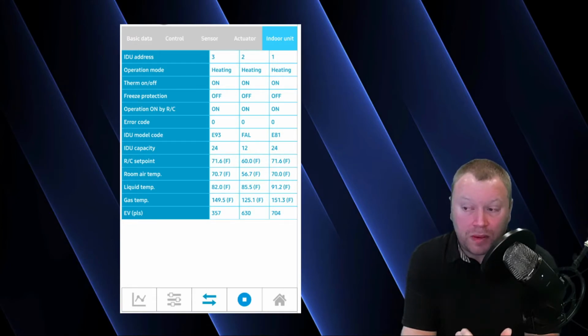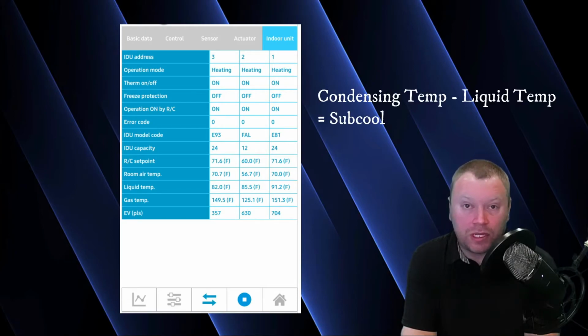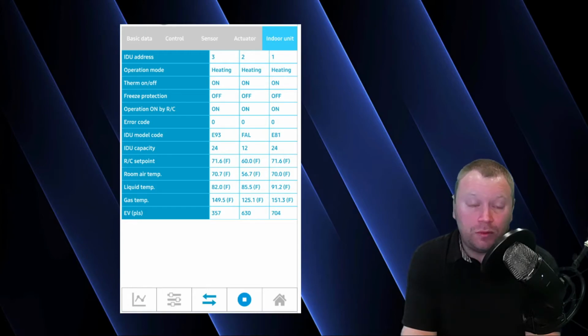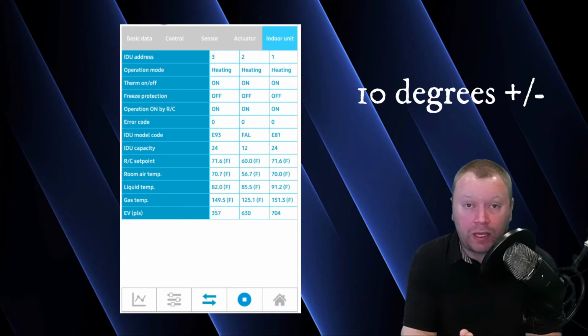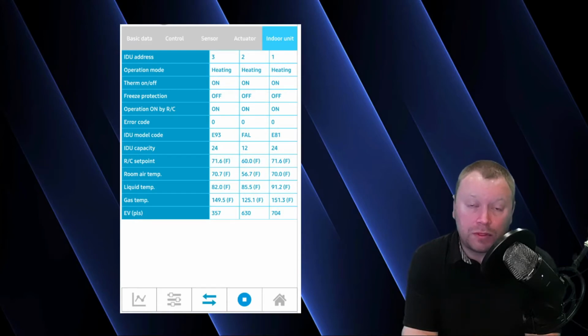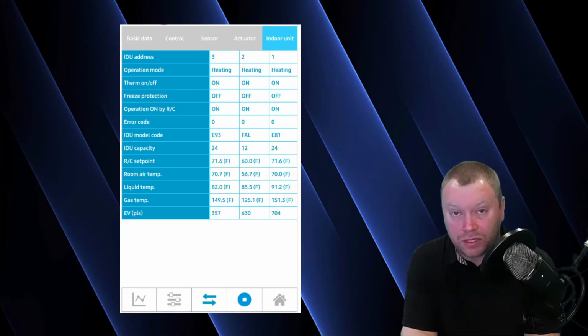And if we compare that to the condensing temperature, 112 degree condensing temperature, that number is going to come into play here because it's that number, 112 degrees minus the indoor unit liquid temperature, which is going to give us the amount of subcooling we have at that zone. Now, generally, we would like to have 10 degrees of subcooling at each indoor unit, but that number can vary anywhere from 5 all the way up to approximately 27 degrees. And that doesn't mean that if you have a 27 degree subcooling number, that's good. It just means that it isn't cause for alarm. Usually anything between 10 and 15 is more ideal.